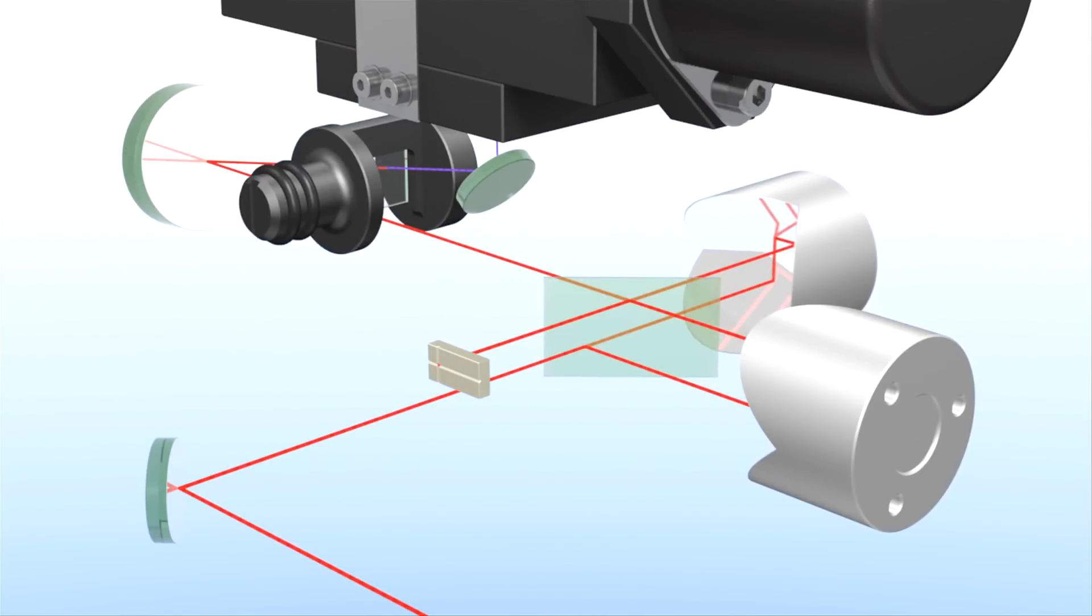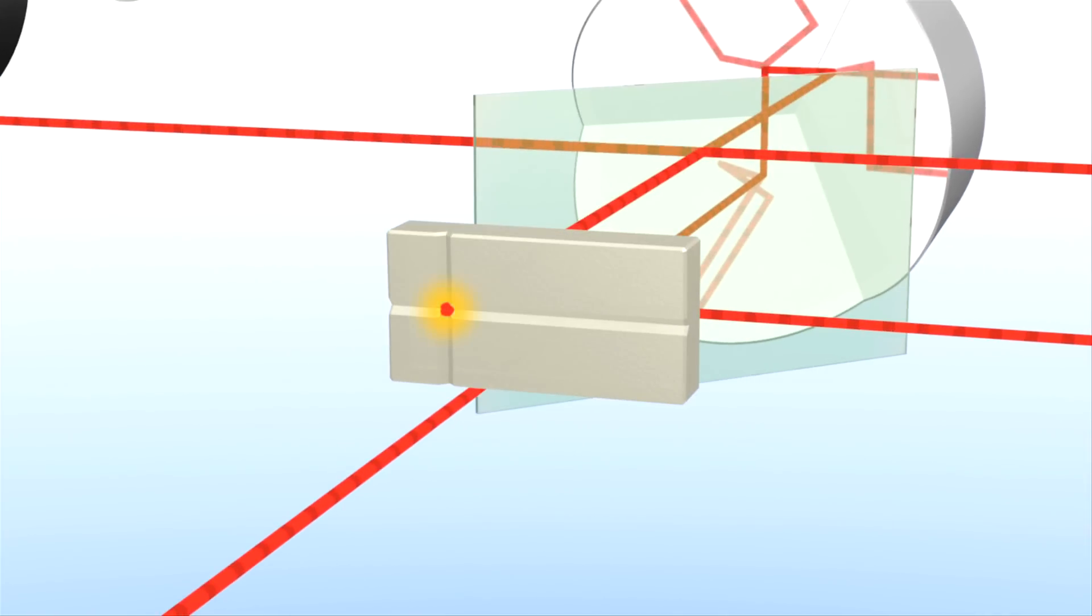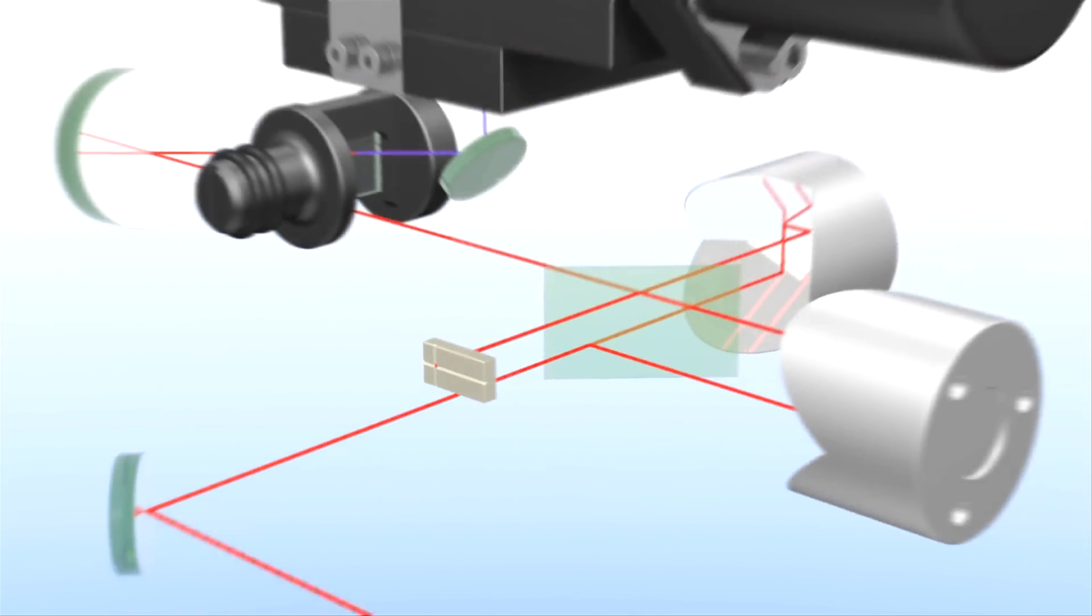In collinear mode, both output beams overlap before they reach the crystal. That was useful during setup, because it lets you align the incoming laser path by only focusing one beam in the crosshair. But collinear mode produces a lot of interference and background signals.